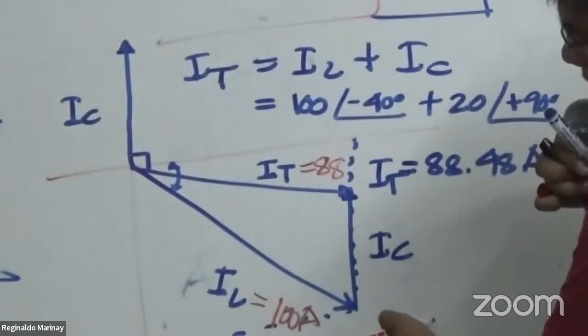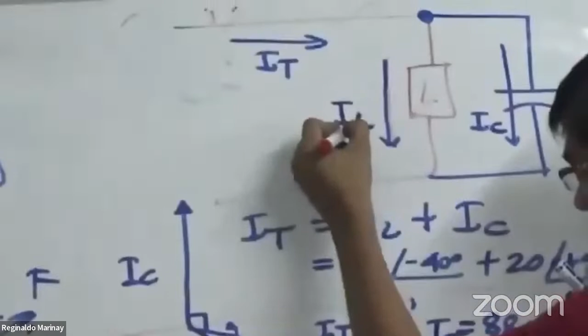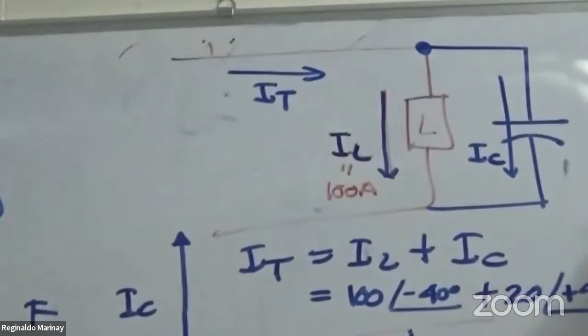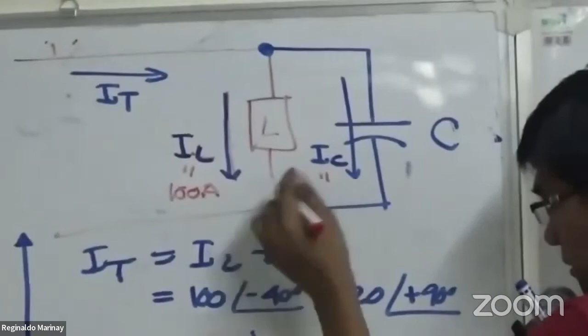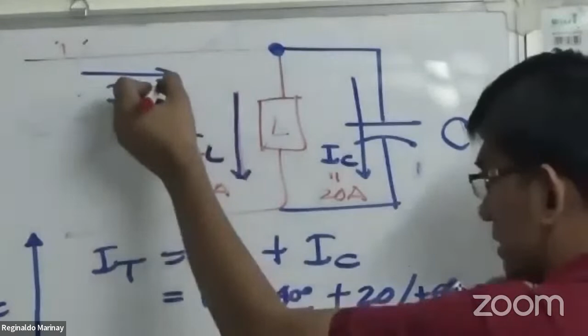You see? Before, you're getting 100 ampere. Remember, the 100 ampere is the current drawn by your load, and the 20 ampere is the leading current drawn by your capacitor. Your total current will just be around 88.48 amps.